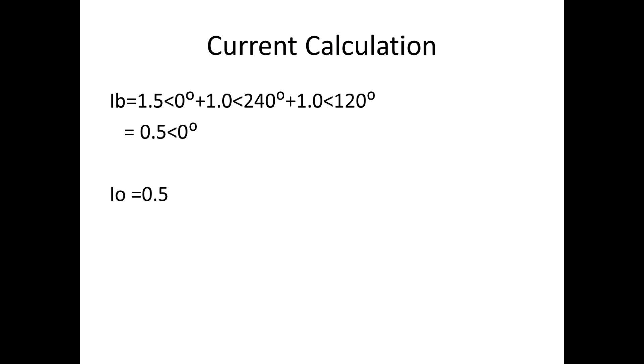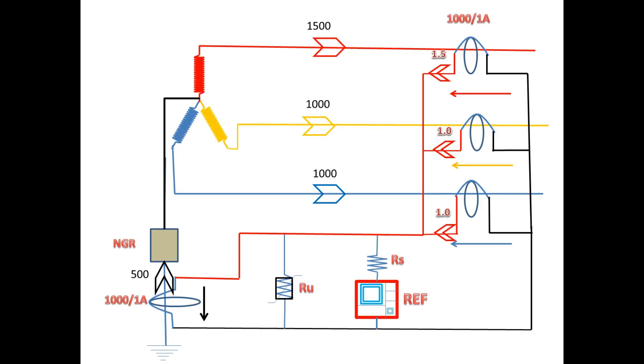For I0, the current is 0.5 amps. If we see both currents I0 and IB, they have equal magnitude and the same angle. So the current flows outward and will not enter the REF relay. The RS resistor is also one reason. In this case, the relay will read 0 amps so it will not trip.